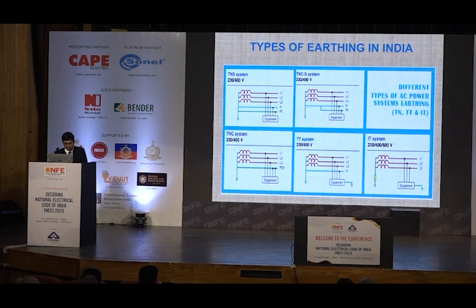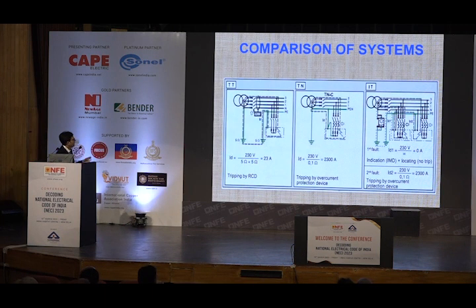And for every system, tripping or isolation, automatic disconnection is very important. For your TT system, the only choice you have to make it automatically disconnect is RCD. For your TN system, it is by overcurrent protection. And for your IT systems, you need insulation monitoring systems, IMD devices, to take care of the insulation of your system.